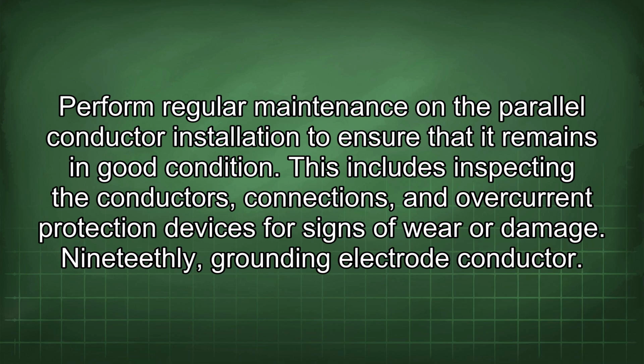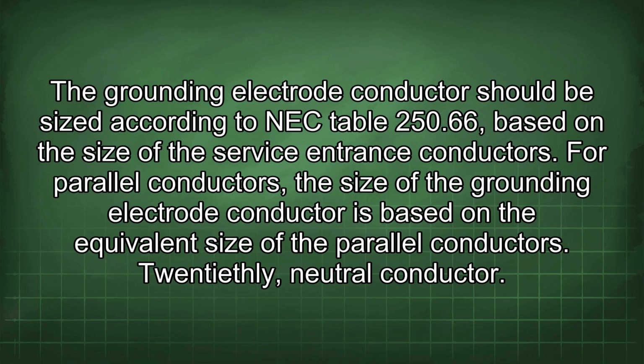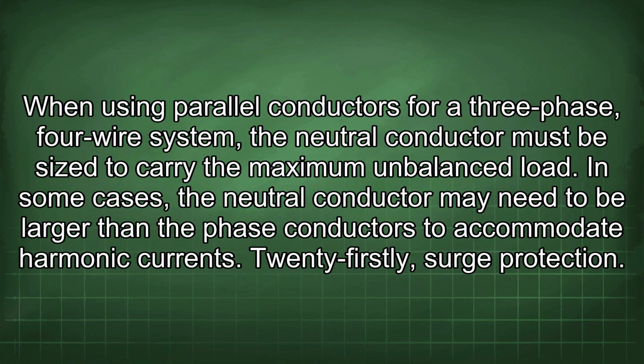19th, grounding electrode conductor. The grounding electrode conductor should be sized according to NEC Table 250.66, based on the size of the service entrance conductors. For parallel conductors, the size of the grounding electrode conductor is based on the equivalent size of the parallel conductors. 20th, neutral conductor. When using parallel conductors for a three-phase, four-wire system, the neutral conductor must be sized to carry the maximum unbalanced load. In some cases, the neutral conductor may need to be larger than the phase conductors to accommodate harmonic currents. 21st, surge protection.